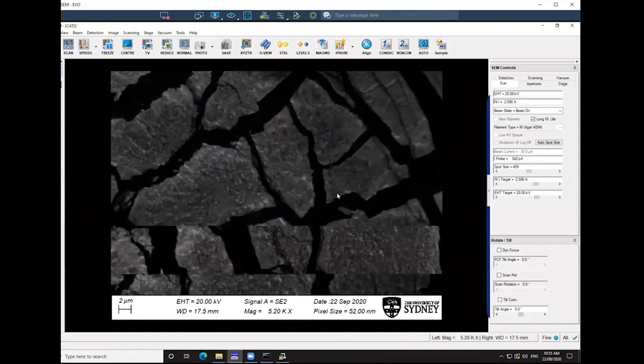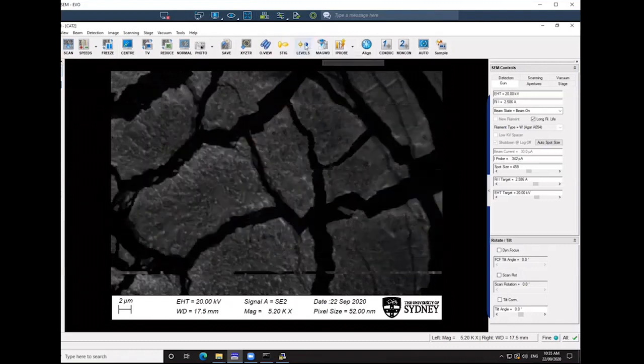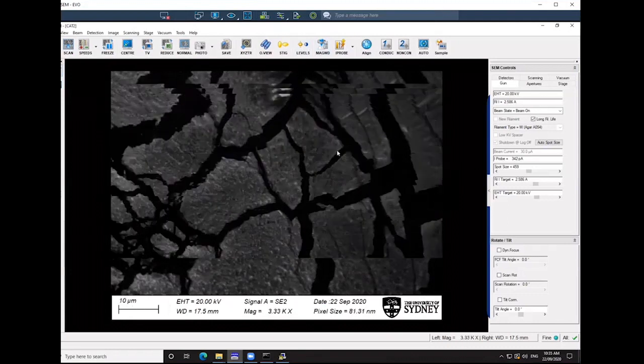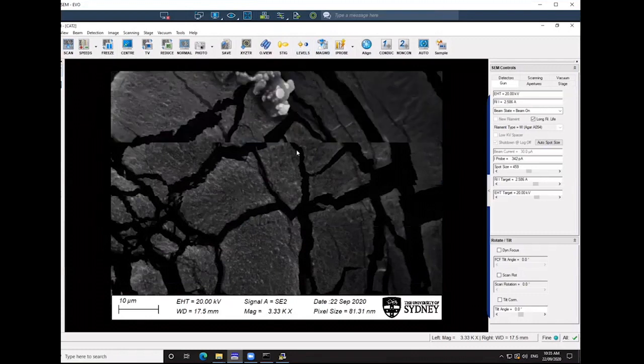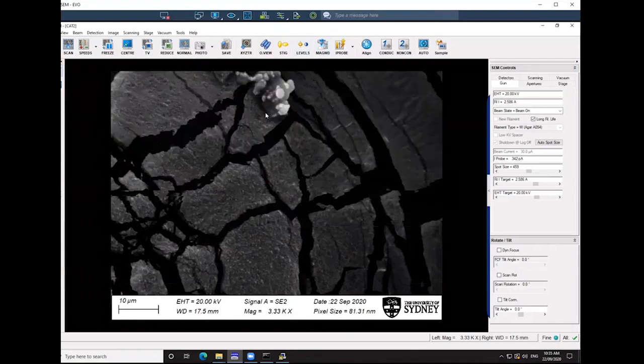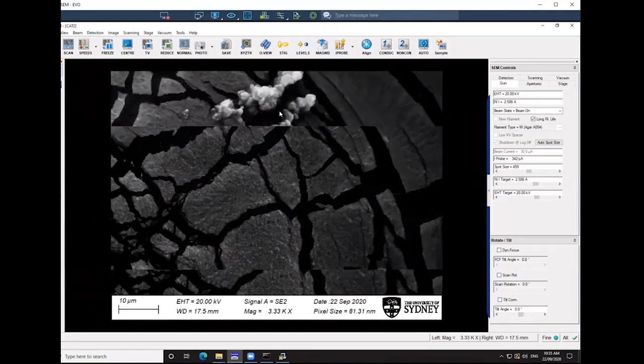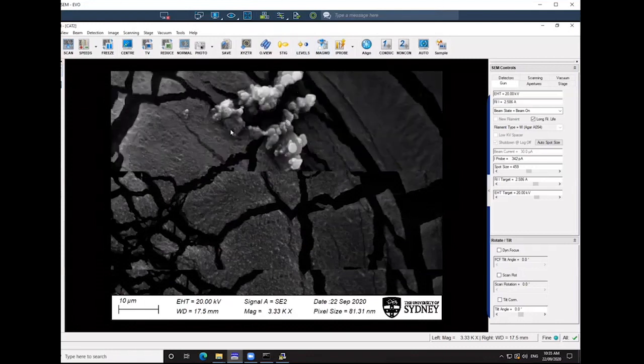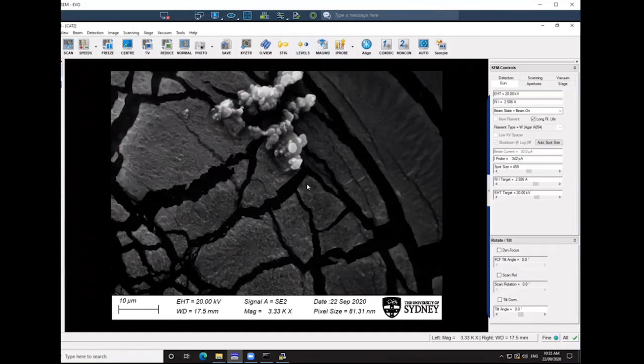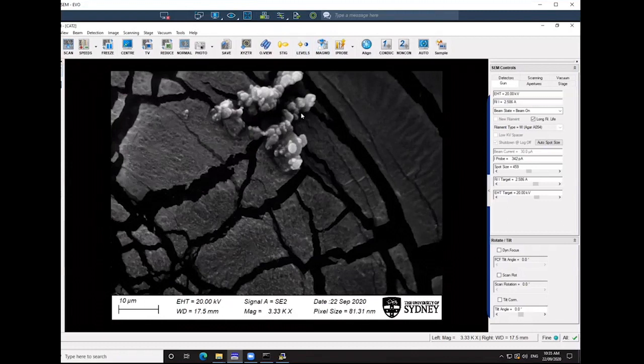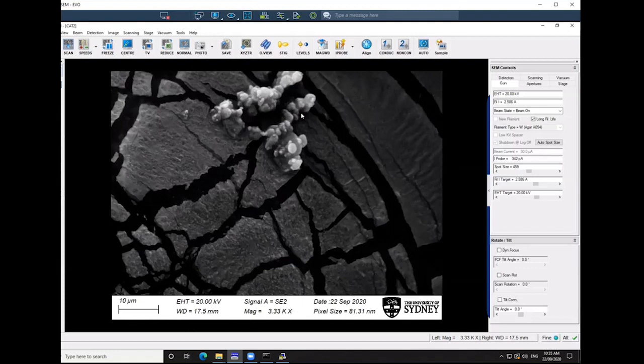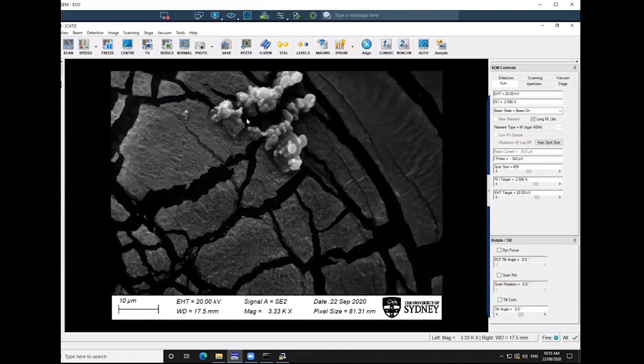Let's zoom out a little bit there. Things like this, where this particle is sticking up, it's not a flat surface. EDS requires a flat surface, and whenever you have this surface roughness, you'll get shadowing because X-rays are pretty much a line of sight to the detector. Because the detector is only on one side of the sample, any X-rays that are generating on the opposite side may get shadowed, and we won't get an even signal.